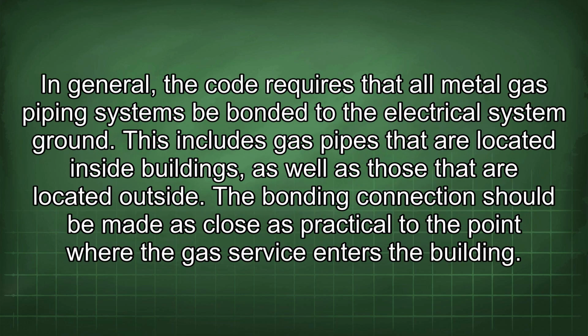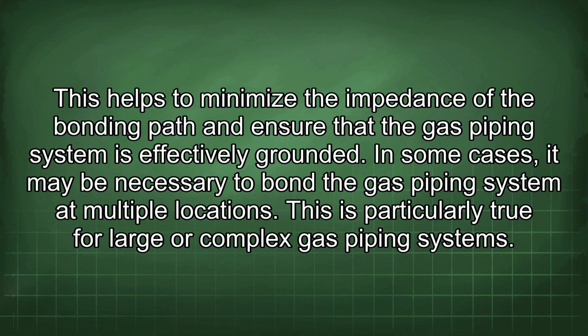In general, the code requires that all metal gas piping systems be bonded to the electrical system ground. This includes gas pipes that are located inside buildings, as well as those that are located outside. The bonding connection should be made as close as practical to the point where the gas service enters the building. This helps to minimize the impedance of the bonding path and ensure that the gas piping system is effectively grounded.